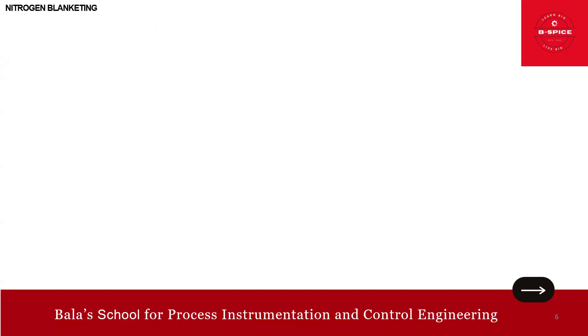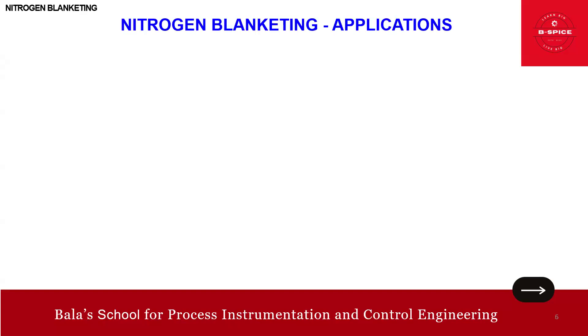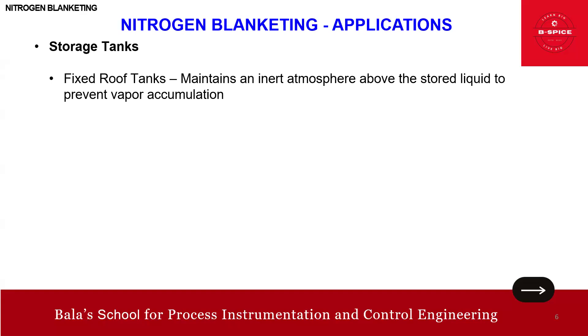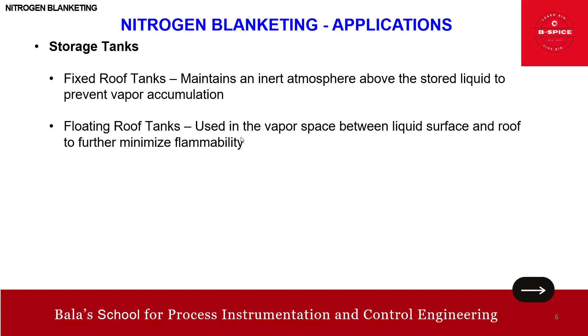Now for the applications. In storage tanks, there are fixed roof tanks and floating roof tanks. For fixed roof tanks, nitrogen maintains an inert atmosphere above the stored liquid to prevent vapor accumulation. For floating roof tanks, nitrogen is used in the vapor space between the liquid surface and the roof to further minimize flammability.